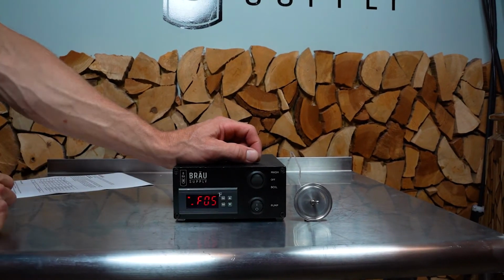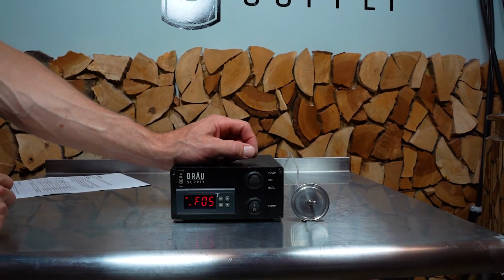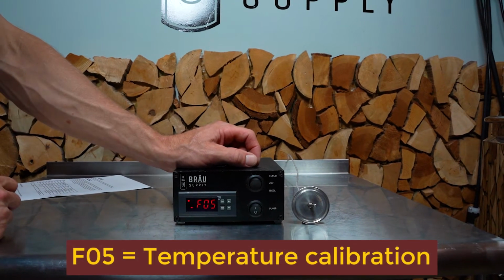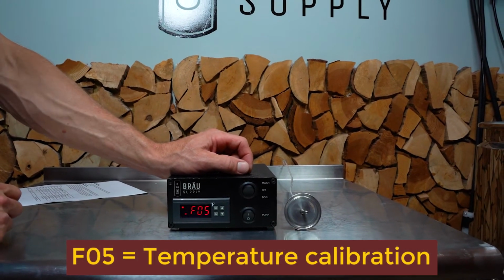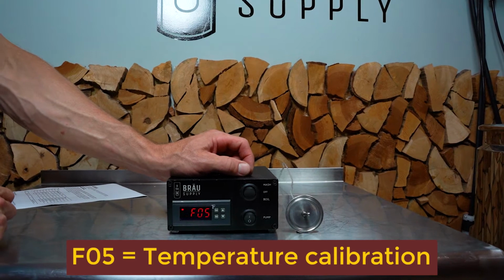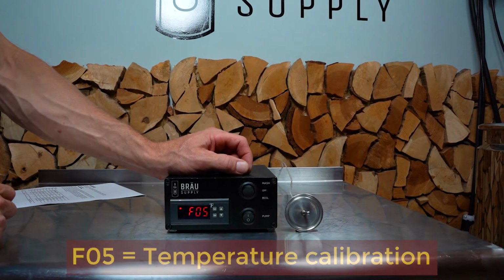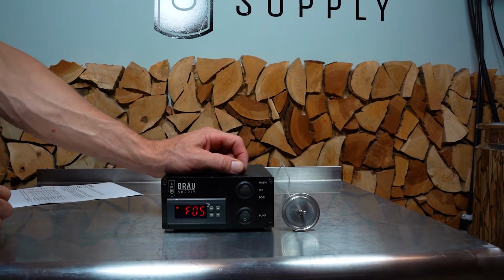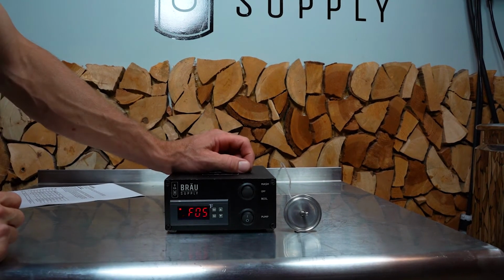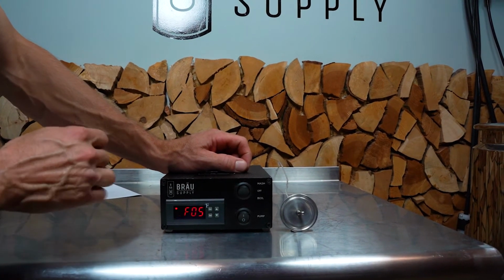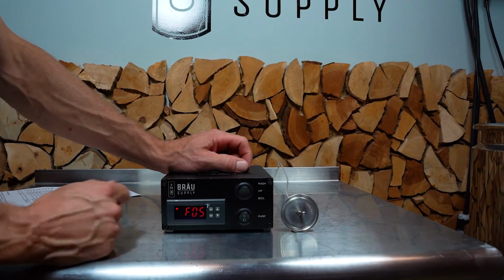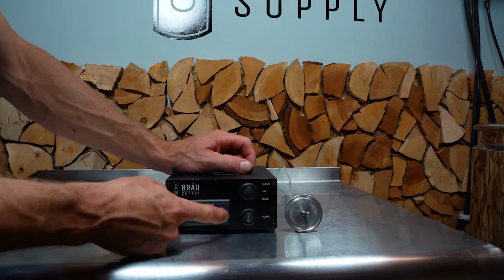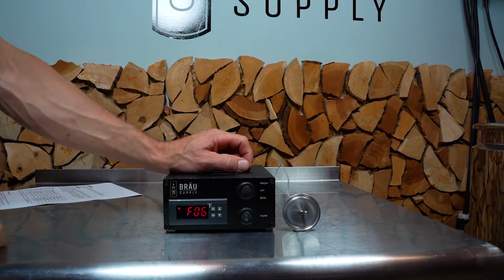Now I'll press up to F05. F05 is your temperature calibration. Again, these units are pre-calibrated fairly accurately. I find when users try to attempt to quote-unquote fix the calibration, they tend to just make things not work as well as they do out of the box. So I generally leave that one alone.